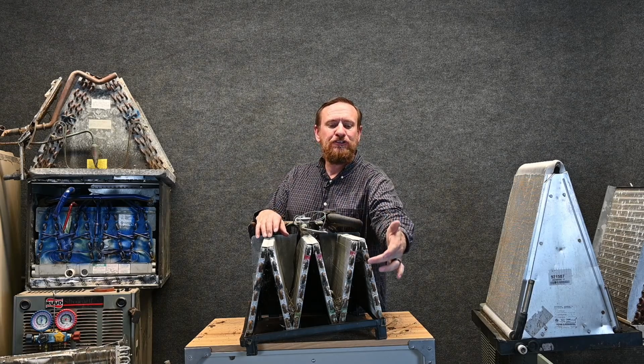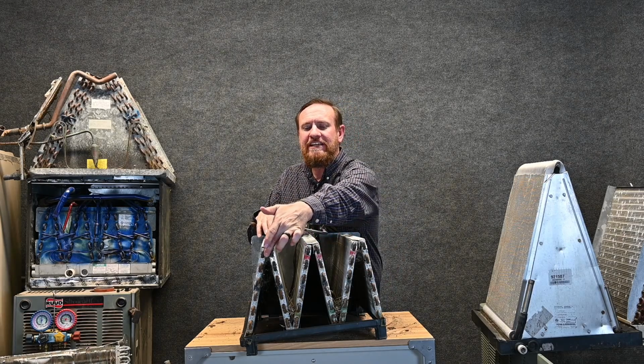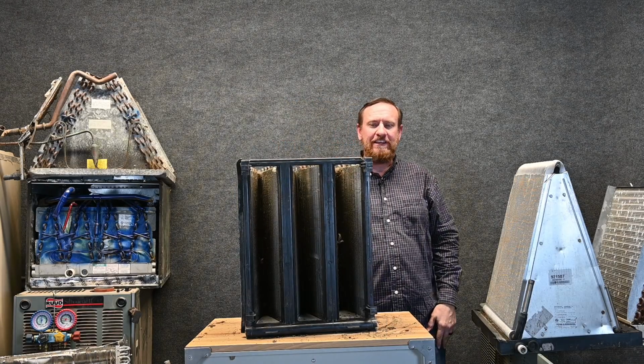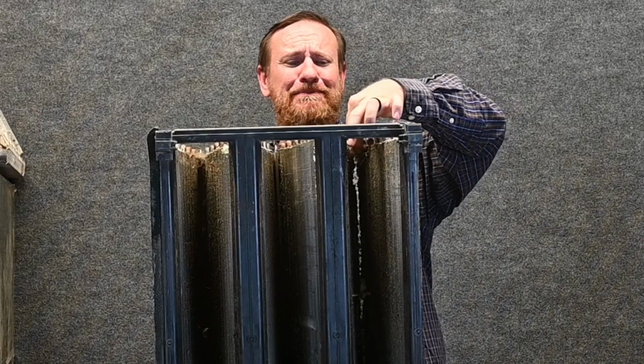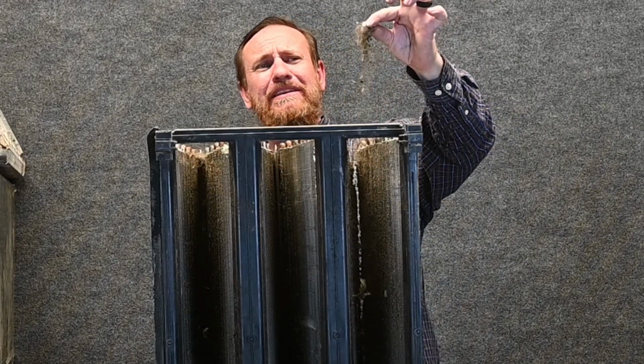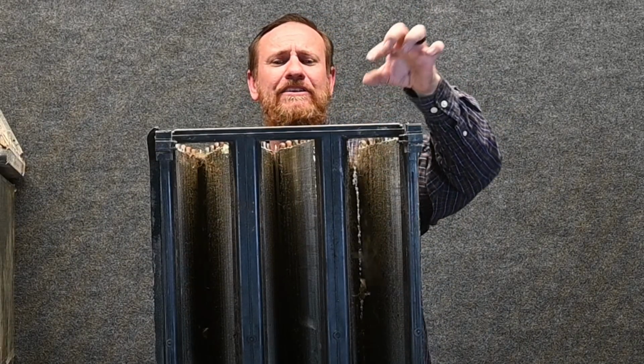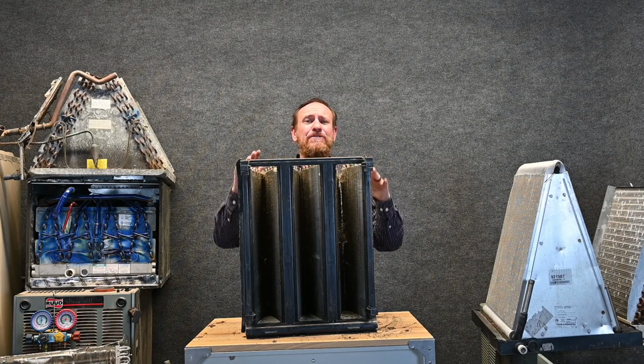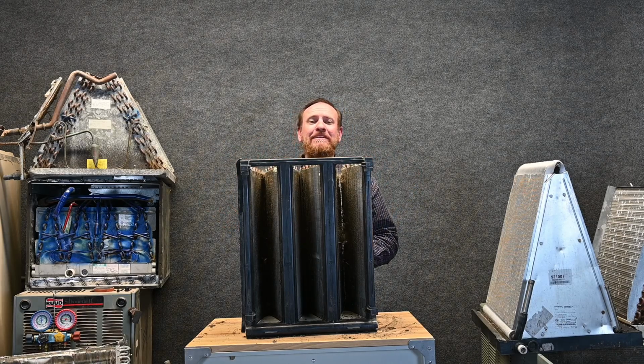With these evaporator coils, you have to check between each one of these individual little A's to see how dirty it is. And we can see there's a significant amount of dirt built up in here. Completely clogged up with somebody's hair. So definitely an issue. Now, should these coils ever get dirty? No, they should never get dirty. How many times should you have a coil cleaned? Never. An AC coil should never need to be cleaned.